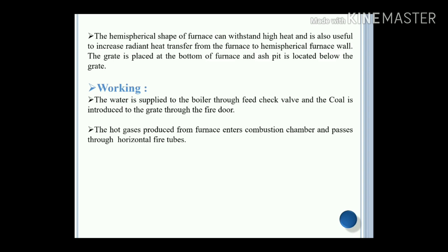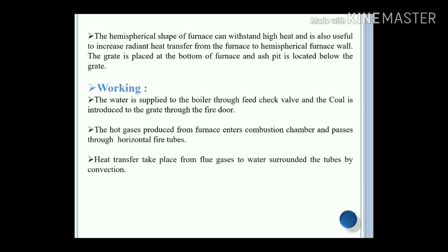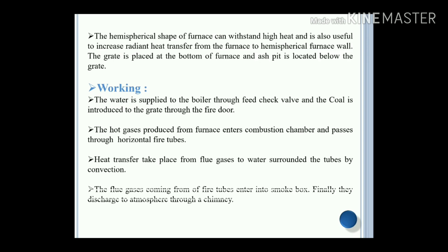The hot gases produced from the furnace enter the combustion chamber and pass through the horizontal fire tubes. Heat transfer takes place from the flue gases to the water surrounding the tubes by means of convective heat exchange. The flue gases coming from the fire tubes enter into the smoke box and are finally discharged to the atmosphere through a chimney. The ash formed is collected into the ash pit.